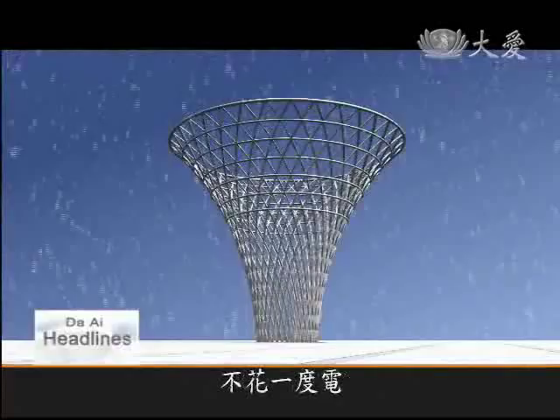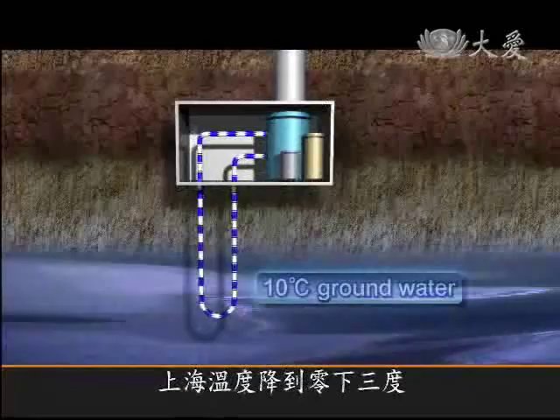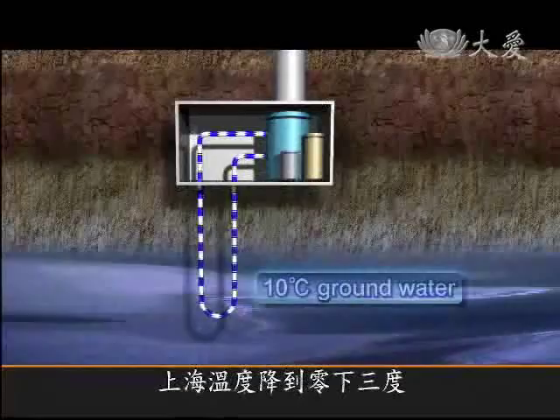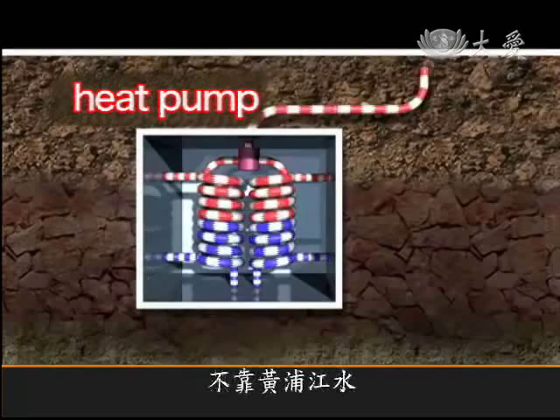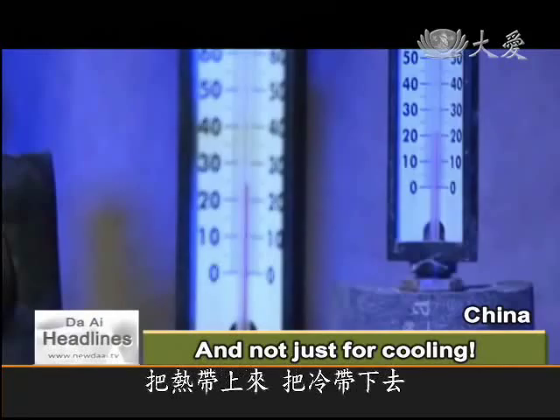During winter, Shanghai's temperature sometimes drops to 3 degrees below Celsius zero. For this, Huangpu waters aren't used; instead the system draws on the natural heat of the earth below. Heat is taken from the groundwater, pumped up to warm the outside air, and after it cools, it's pumped back down to the cisterns below. By bringing the heat up and dropping the cold down, the Expo Axis avoids any need for external heaters while keeping a comfortable temperature throughout the cold winter months.